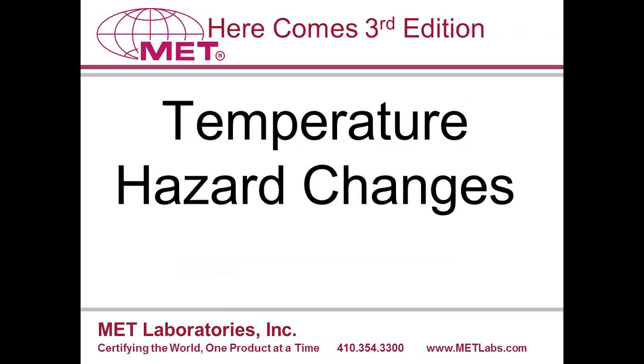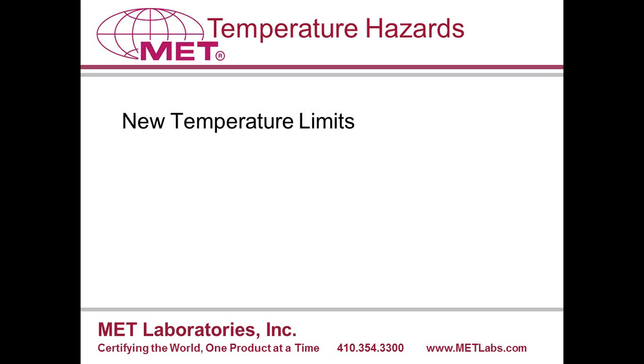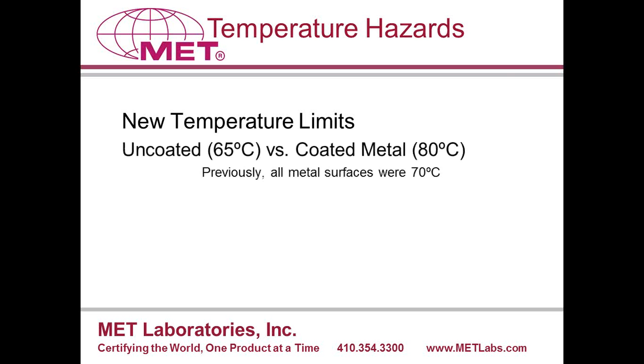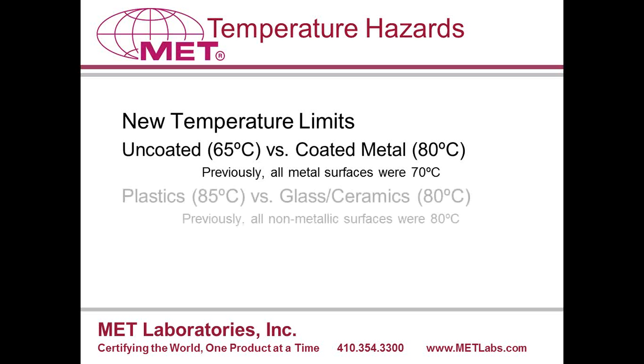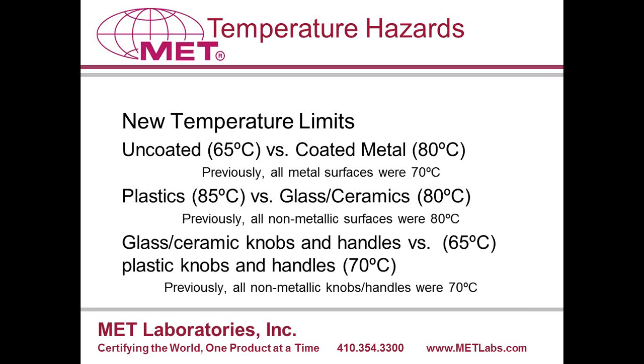Now let's talk about changes to the temperature test. The 3rd edition has become more specific in how it recognizes different materials and how likely they are to burn the skin. Uncoated and coated metal are distinguished, and coated metal can be at a higher temperature, while uncoated metal has a lower temperature limit. Similarly, plastics versus glass and ceramics are distinguished. Plastics can be at a higher temperature. The requirements for glass and ceramic knobs have become more stringent, now reduced from 70 degrees C to 65 degrees C.